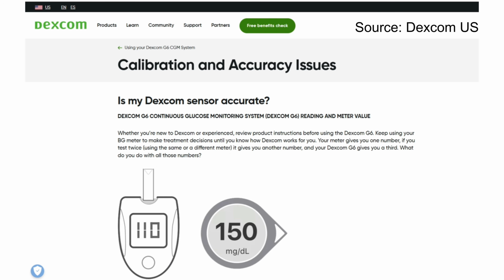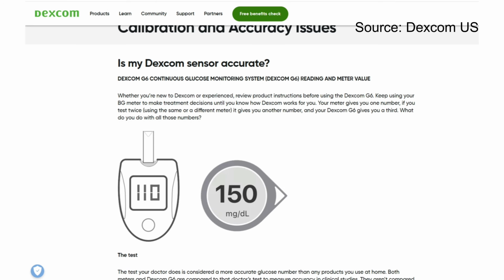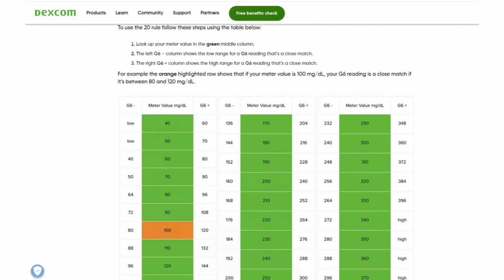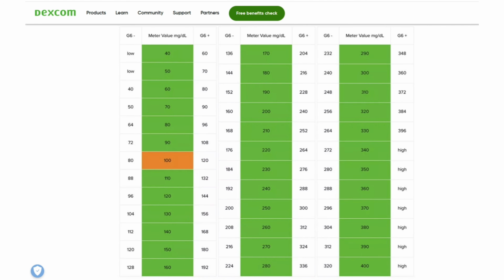Another consideration is that the rule of thumb is plus or minus 20% is still considered accurate. Dexcom has a really good illustration. Here you see that if a CGM reading is 80 to 120 milligrams per deciliter and a finger stick is 100, it's still considered accurate. I know that this frustrates a lot of people, and I get it. My rule of thumb is that if my blood sugars are consistently 30 milligrams per deciliter off from my CGM, I will calibrate it, but that's just me.